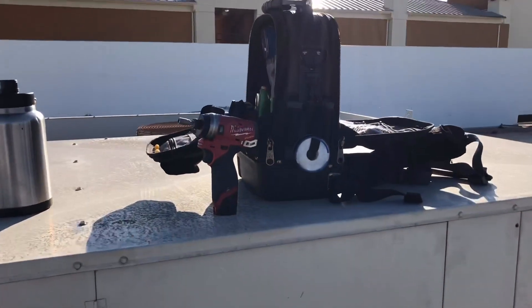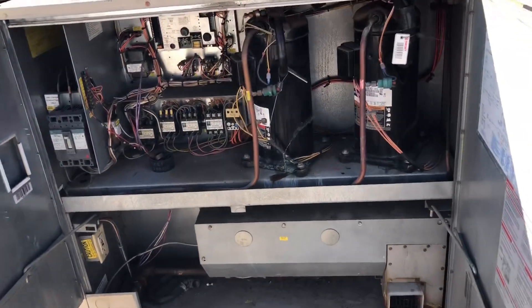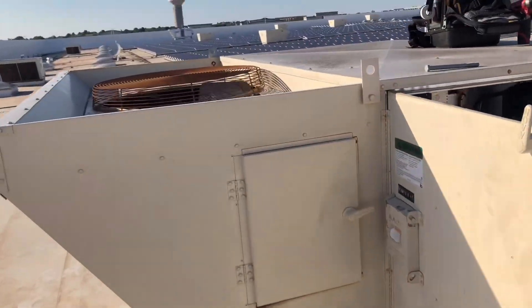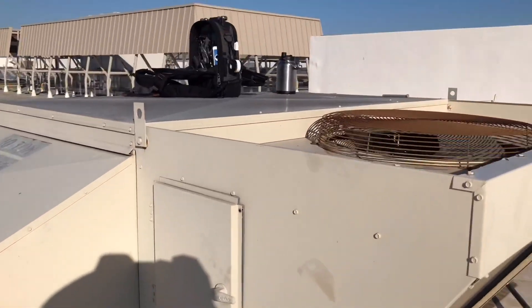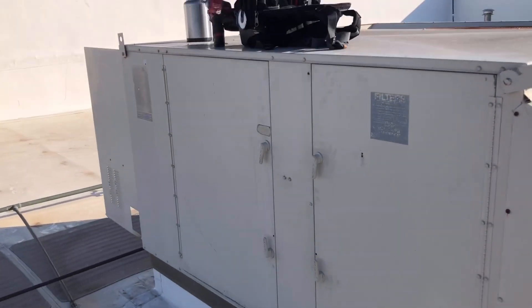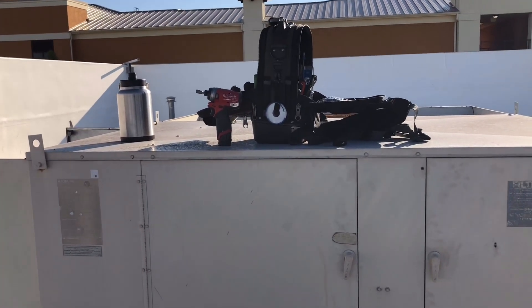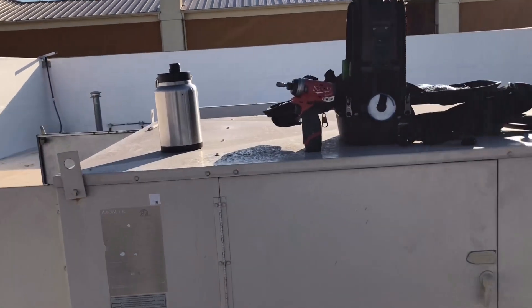On a Wednesday they don't take any calls after 5 o'clock. So at this point, because I do have a 20 degree delta T, everything is running, and my board is showing all communication as normal, we are going to place this call on what we call a follow-up and give them a call tomorrow. Possibly if they need us to come out here we will come back out, check the sensors and all. I also got a call for an open air case at a different location — I'll see if I can drag you guys along to make it a two-call video.